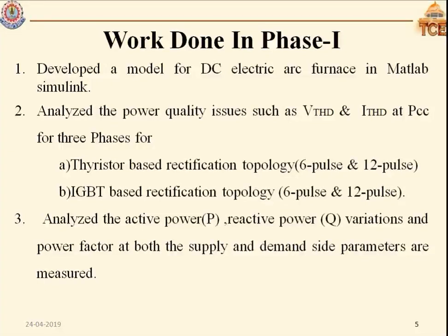This is the work that we have done in phase 1 of the project. In phase 1, we considered the utility side, and on the industry side, how an electric arc furnace is fed. In general, the electric arc furnace is fed by two types of supply: the conventional AC one, and the DC electric arc furnace supply. In phase 1, we considered a DC electric arc furnace, which is fed by a thyristorized converter, and we analyzed the power quality issues such as voltage THD and current THD at the point of common coupling, PCC, where the electric arc furnace is connected, from the utility point of view.